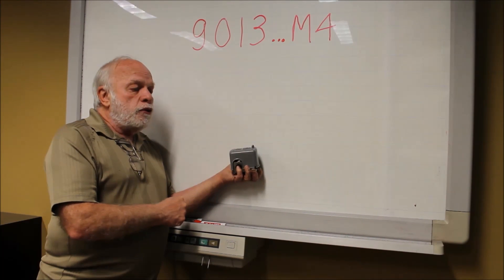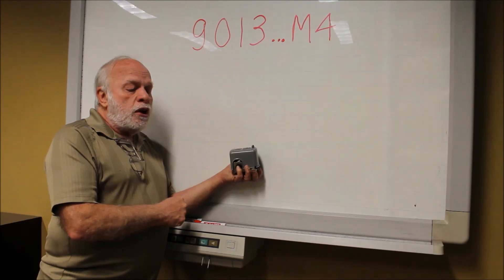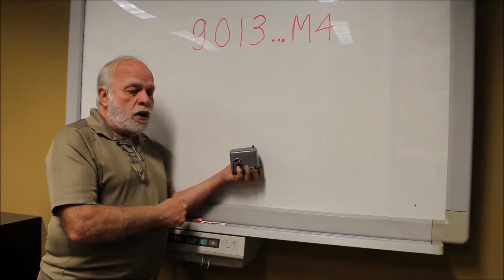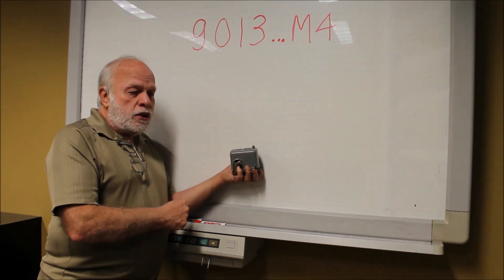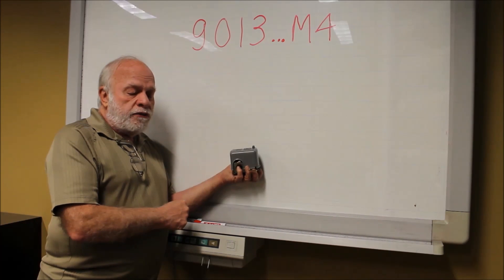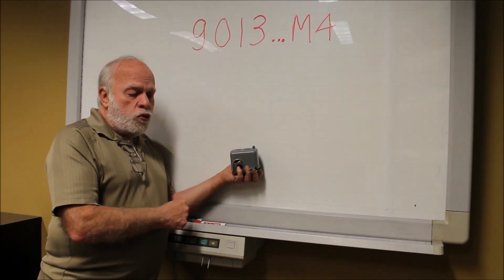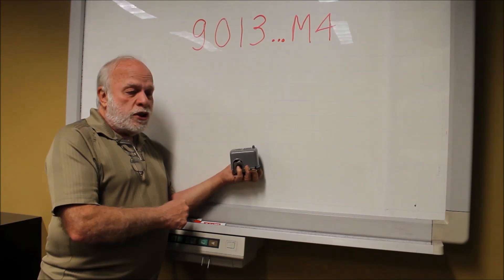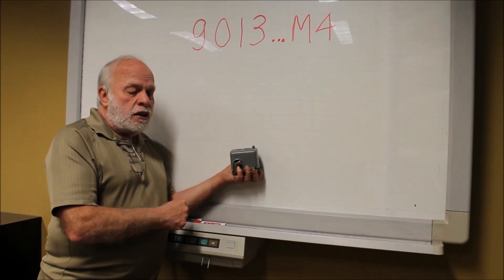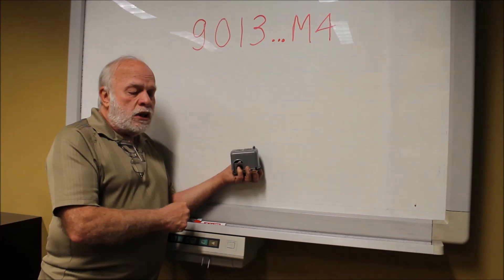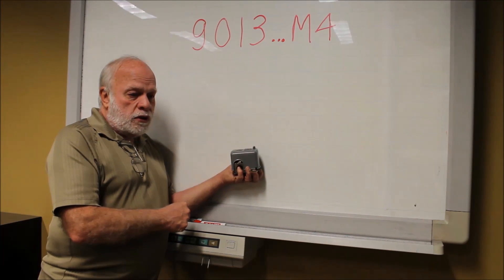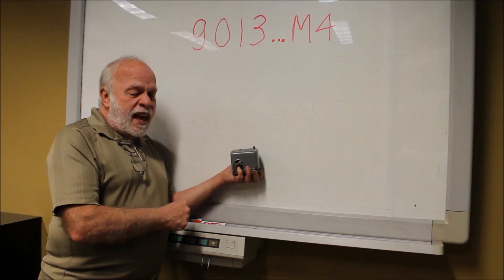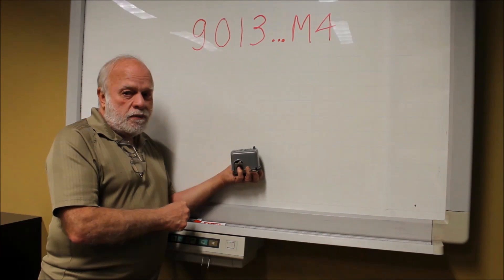There is no way to eliminate the M4 operation on a switch that was manufactured with the M4 form, nor can it be adjusted to anything other than 10 pounds below the cut-in point of the switch, even though that itself can be adjusted.